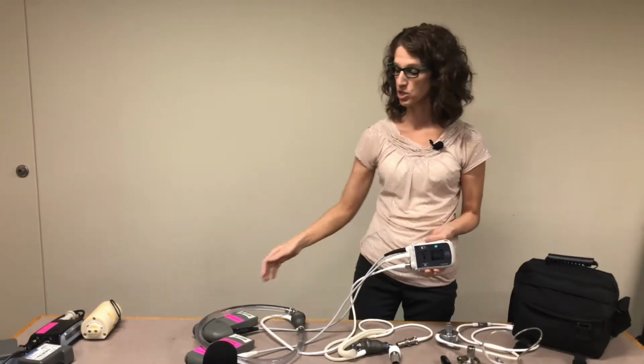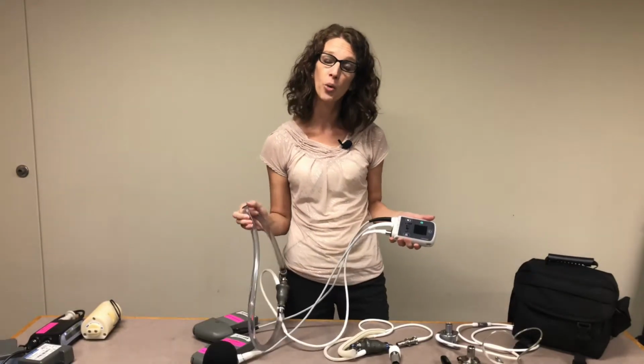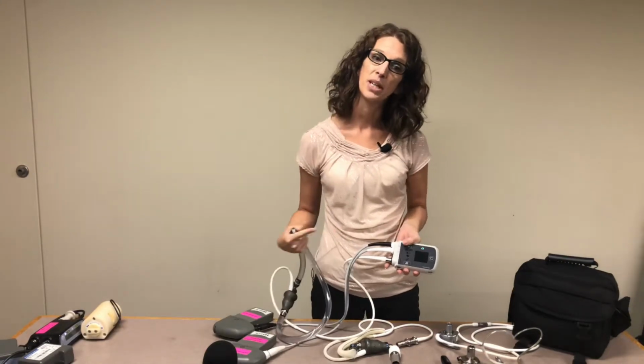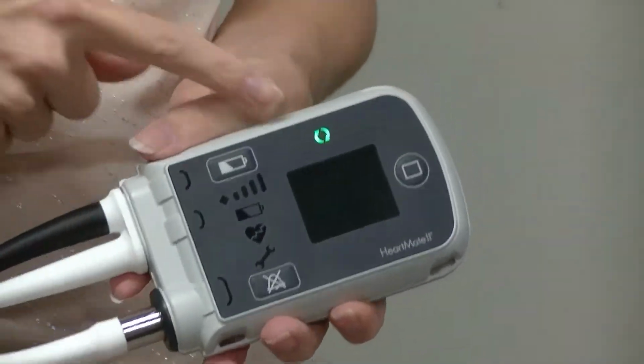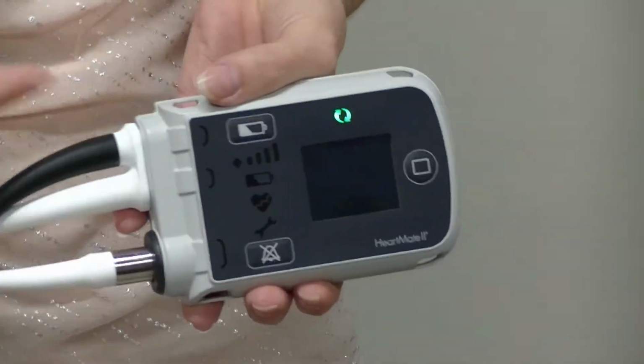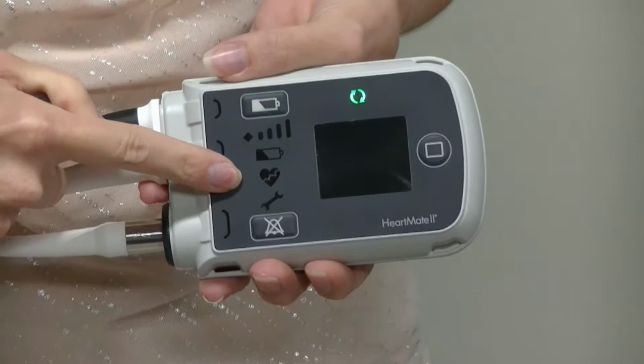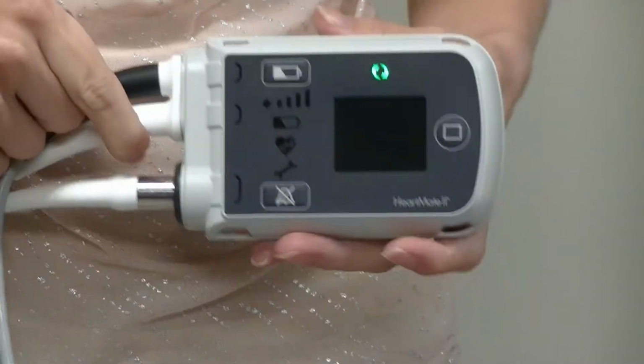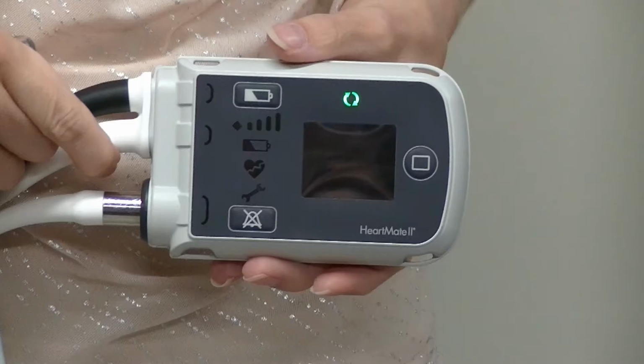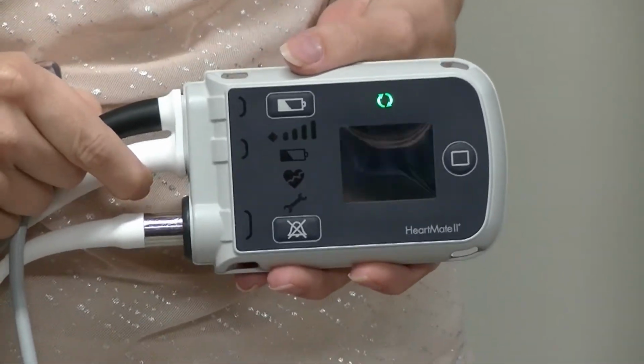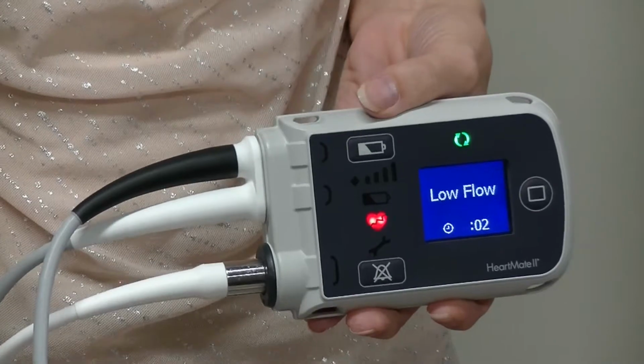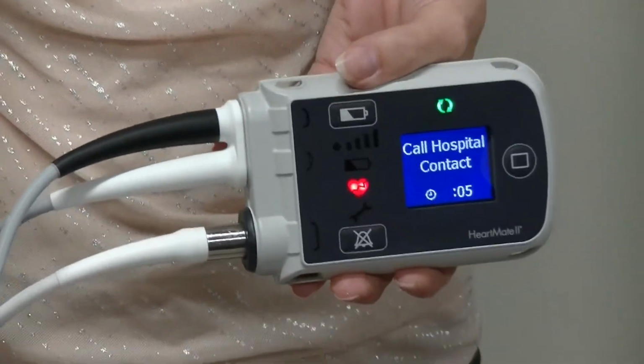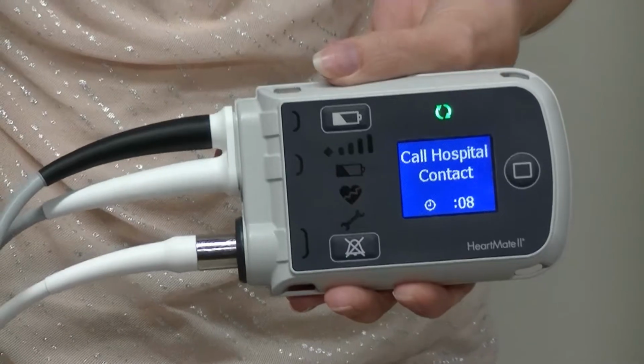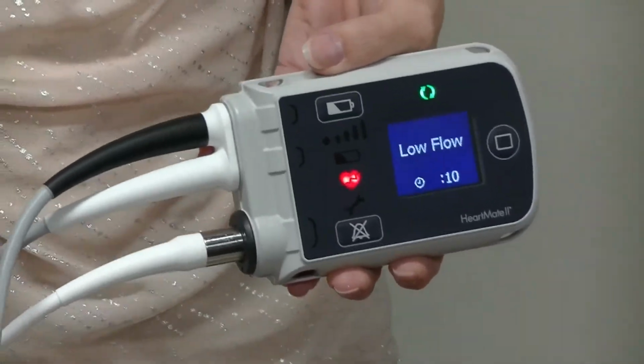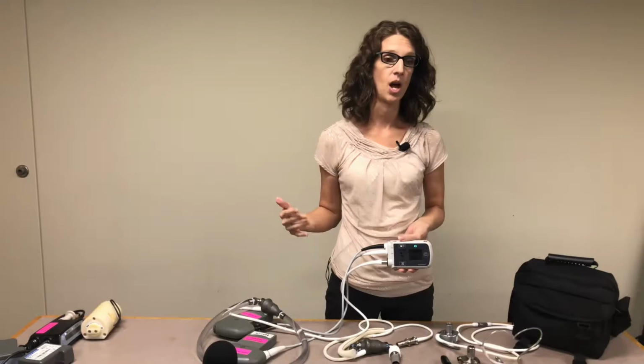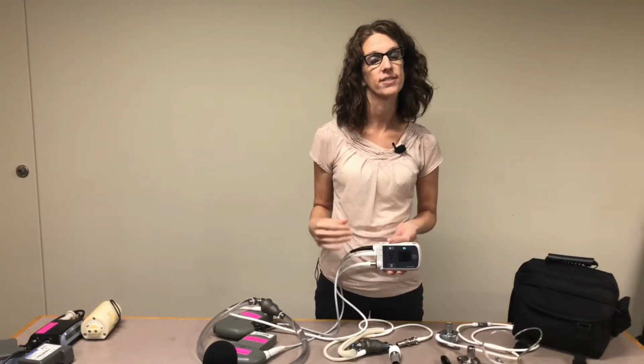If we create an alarm situation where the patient is having low flow, what's going to happen is the VAD will be audibly alarming, but the green light is still going to be on. The low flow indicator on this device is going to be this heart. It's going to show up red, and on the screen it's going to say low flow, call hospital contact. If that's the case, we want you to call the VAD coordinator and look for some advice. If the low flow resolves with fluid or any other intervention, the alarm will just stop automatically.